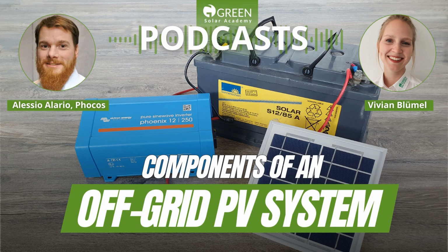And for very large systems, you can build a distributed mini grid. So you might have a large central battery in a village connected to multiple off-grid inverters, and then multiple PV arrays which could be distributed throughout the village. I think those are the two real use cases for AC coupling. Certainly only, in my opinion, relevant for system sizes well beyond 5 kilowatts. I would start thinking about AC coupling at maybe 20, 30 kilowatts, something like that.